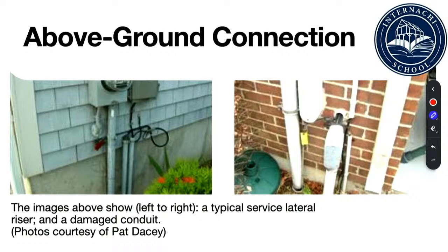Above ground connections as it comes into the house. This is, again, nothing should be loose. Everything should be tight and secured, no wiggles. And I hear people saying that, well, yeah, of course we don't want that coming apart. That's going to cut the wires and it's going to short it out. Well, it's more than that. If those wires do come loose and they touch and energize this, there's no way to get that back to trip the fault. A lot of people don't realize that if I energize this portion here, it's not going to trip the breakers. I'm not getting power going through the main disconnect. And I'll talk more about that when we get to grounding and bonding and what we're looking for with those items as well. All right. Typical service lateral and a damaged conduit on the right side.